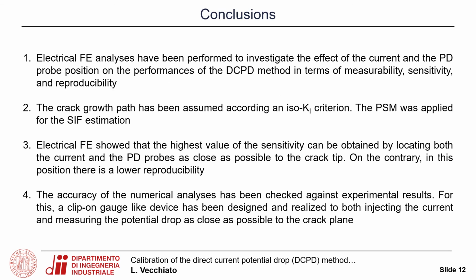So coming to the conclusion, electrical finite element analysis has been performed to investigate the effect of both the current and the potential drop probe's position on the performances of the DCPD method applied to single edge crack round bars. The evaluation was performed in terms of measurability, sensitivity, and reproducibility. The crack path applied for doing this was assumed to be according to the ISO-K1 criterion. And for evaluating the corresponding crack path, the PSM was applied for the estimation of the stress intensity factors.